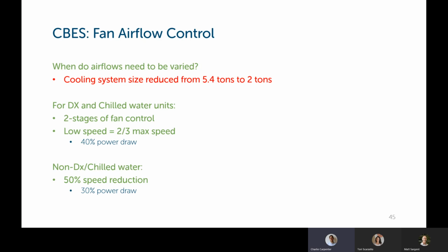Airflow control for commercial buildings. So when do you need to vary the airflow in a building? Any cooling system that is 2 tons or more needs to have variable air flow. And that has been reduced from 5.4 tons from the current 2015 code. So that'll be applicable on many more systems on commercial buildings.